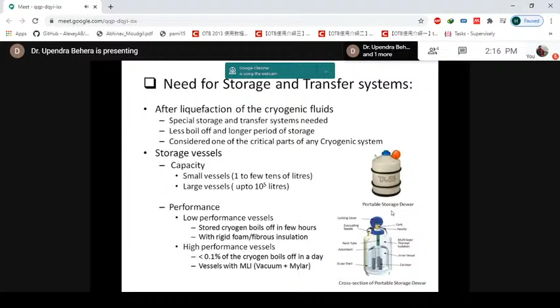These small dewars are generally suspended from the top, from the outer shell or outer vessel. They are not closed fully because there is no safety arrangement; the lids are loosely fitted with some cork material so that thermal conductivity is less, and whatever cryogen is getting boiled off can easily pass on. Sometimes they put slits, making passages in the cork so the gas can easily escape. This is the locking cover, just to close it.